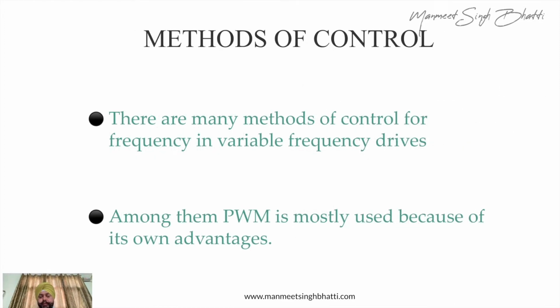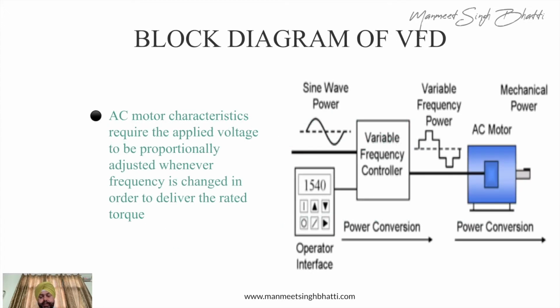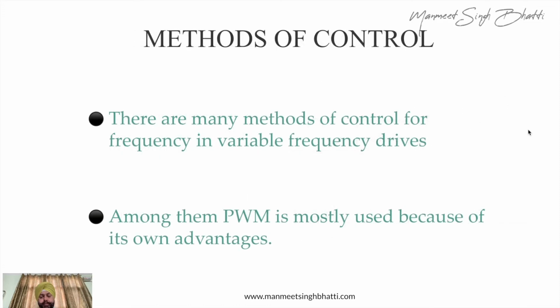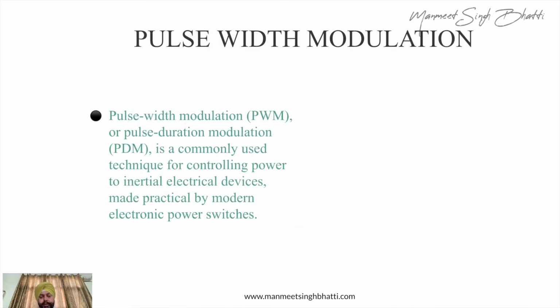Now there are different methods where you can use frequency control, but the most used and best method for the frequency is pulse width modulation. Most of the electronics guys know it, but this is an electrical subject also, because you actually control the width of the pulse that is going out. So if you see the previous slide, you can increase the frequency from here. The width is basically being controlled. Whenever the width of that pulse is controlled, automatically it controls the frequency. It's a standard technology now used everywhere across the globe, and it is highly efficient and highly safe for the motors.